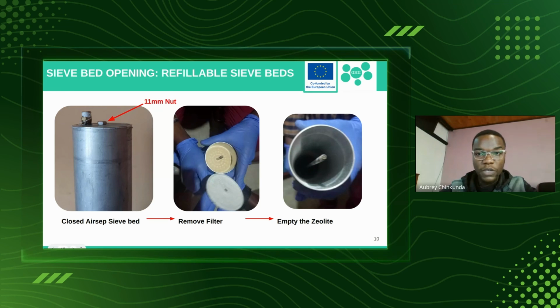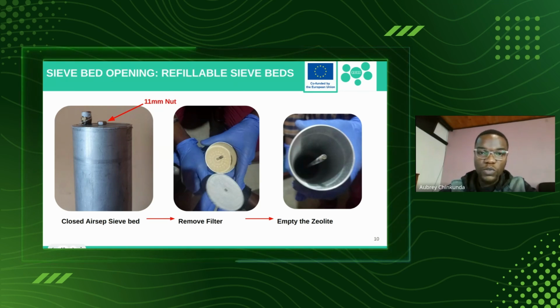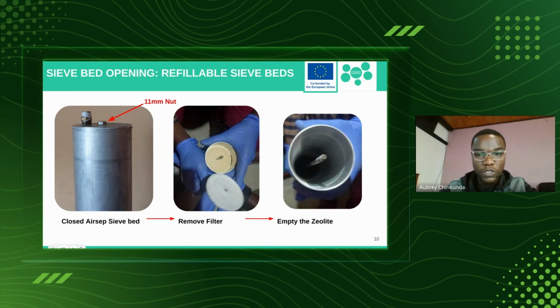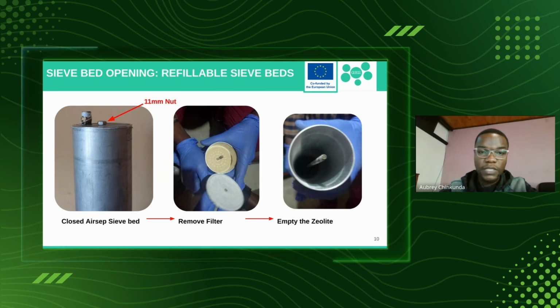If you have a refillable sievebed, you just loosen it up. The only thing you really need to be careful about is the spring, because it has a lot of tension and can hurt you if you're not careful. Loosen either the screw or the nut, then remove the filter, as shown in the middle image. On the far right is the sievebed that has been emptied, with the zeolite removed.